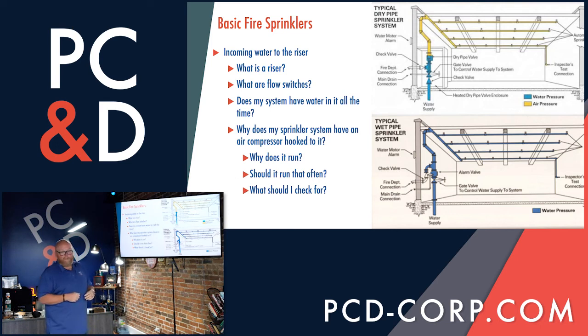One of the things that Travis mentioned earlier is about how the sprinkler system and the fire alarm systems work together. They absolutely do. So you may be asking yourself, how do they work together? For the most part, your fire alarm system is only monitoring smoke heads or heat detectors. They reach a smoke or they reach a heat, it comes back and tells the fire alarm to go off. On the sprinkler system, for the most part, as far as being functional, it is a standalone system. It is a pipe system that's tied to water, it goes throughout the building. It does its job independently of the fire alarm or the smoke detection system or the panel.